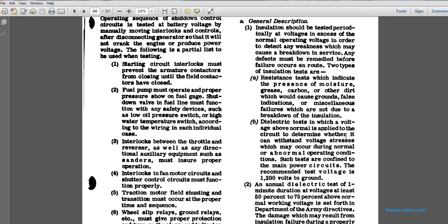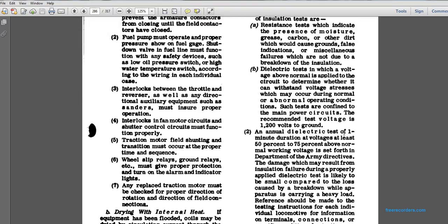Dielectric testing, in which a voltage above normal is applied to the circuit to determine whether it can withstand the voltage stress which may occur during abnormal operating conditions. These tests are confined to the main power circuits. The recommended test voltage is 1200 volts. An annual dielectric test of 1 minute duration, at voltages at least 50 percent to 75 percent above normal working voltage, is set forth in the Department of the Army directive.